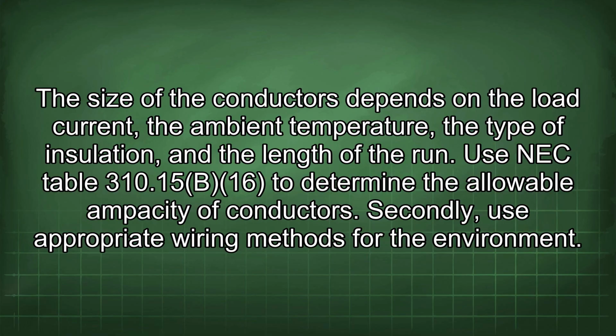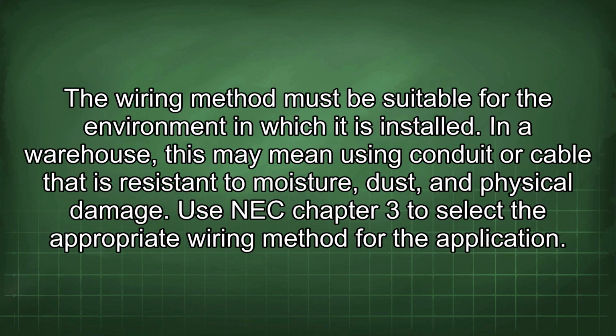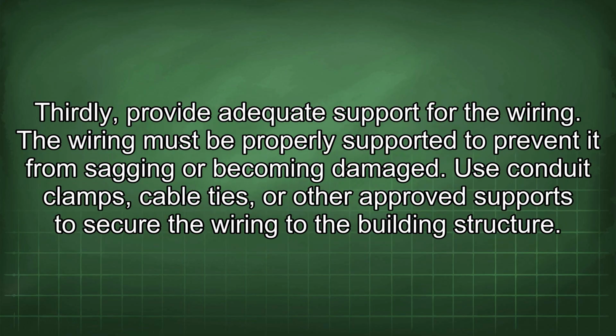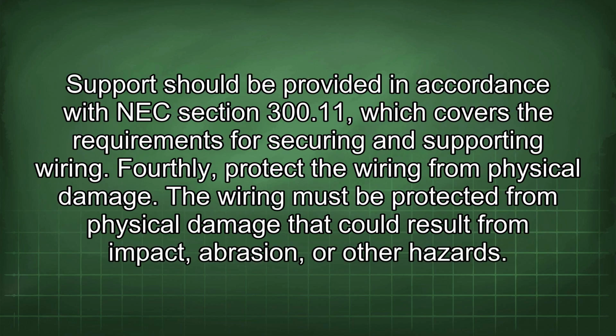Secondly, use appropriate wiring methods for the environment. The wiring method must be suitable for the environment in which it is installed. In a warehouse, this may mean using conduit or cable that is resistant to moisture, dust, and physical damage. Use NEC Chapter 3 to select the appropriate wiring method for the application. Thirdly, provide adequate support for the wiring. The wiring must be properly supported to prevent it from sagging or becoming damaged. Use conduit clamps, cable ties, or other approved supports to secure the wiring to the building structure. Support should be provided in accordance with NEC Section 300.11, which covers the requirements for securing and supporting wiring.